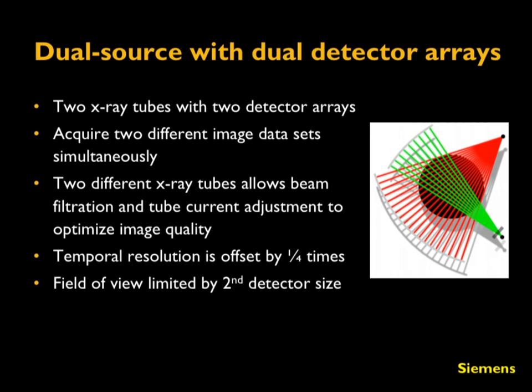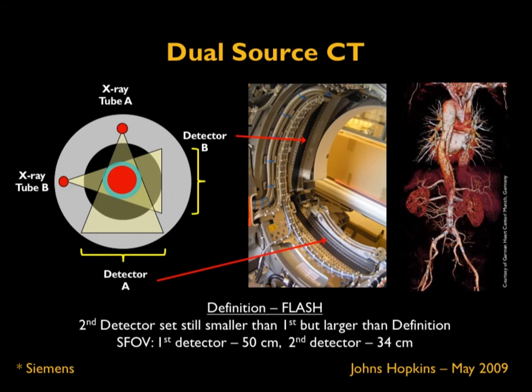One current limitation of this system is that the second detector array is slightly smaller than the primary detector array, resulting in a slightly limited field of view for dual-energy CT acquisition. Shown here is an inside photograph of the CT gantry with two detectors positioned 90 degrees opposite the two x-ray tubes. A key advantage is that each tube can be set at a separate tube voltage, automatically obtaining two x-ray beams of different energies.